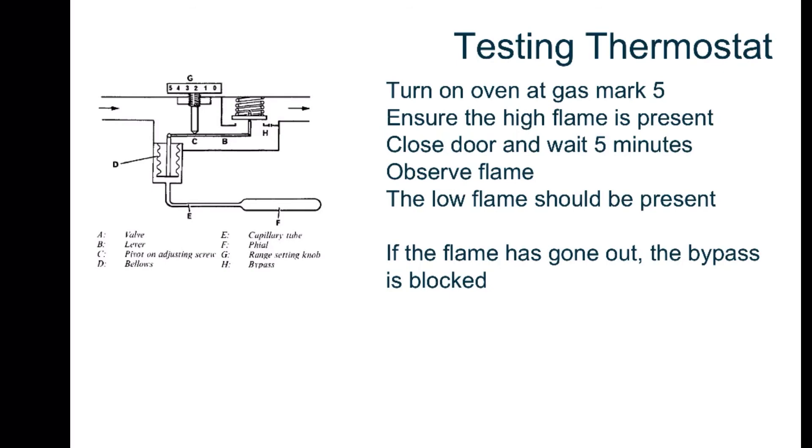Once the high flame is present, you close the door and wait for 5 minutes. During that 5 minutes, the phial, which isn't in the flame but in the oven itself, will get warm and should get warm enough to push its piston and close the main gas valve. The only gas that can get through when that happens is through the bypass, giving you a low flame.